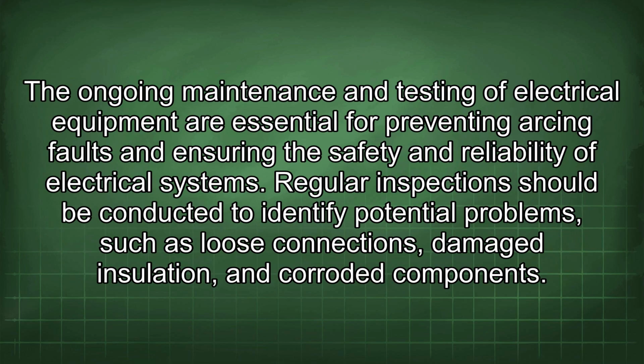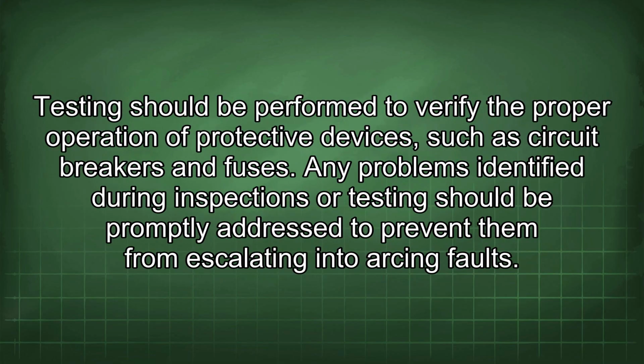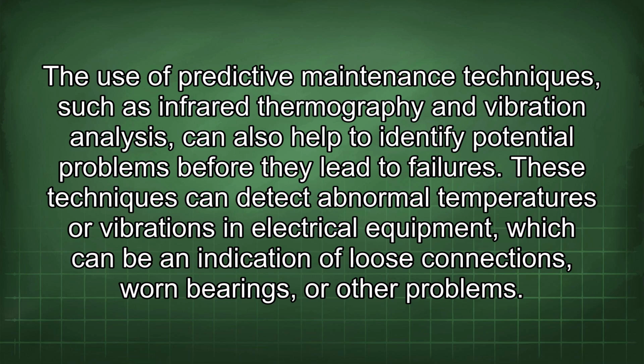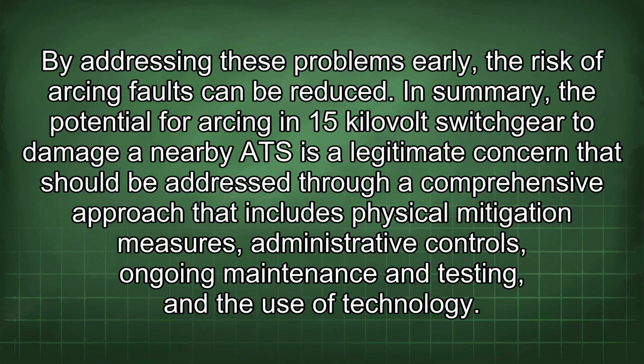personnel. The ongoing maintenance and testing of electrical equipment are essential for preventing arcing faults and ensuring the safety and reliability of electrical systems. Regular inspections should be conducted to identify potential problems such as loose connections, damaged insulation, and corroded components. Testing should be performed to verify the proper operation of protective devices such as circuit breakers and fuses. Any problems identified during inspections or testing should be promptly addressed to prevent them from escalating into arcing faults. The use of predictive maintenance techniques, such as infrared thermography and vibration analysis, can also help to identify potential problems before they lead to failures. These techniques can detect abnormal temperatures or vibrations in electrical equipment, which can be an indication of loose connections, worn bearings, or other problems. By addressing these problems early, the risk of arcing faults can be reduced.